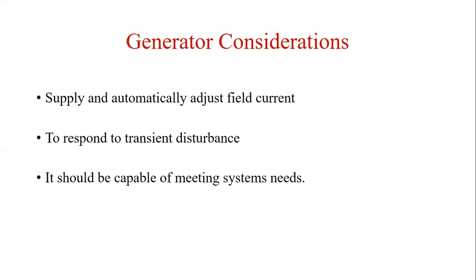In addition, the excitation system must respond to transient disturbances with field forcing consistent with the generator's instantaneous and short-term capabilities. The generator capabilities in this regard are limited by several factors: rotor insulation failure due to high field voltage, rotor heating due to high field current, stator heating due to high armature current loading, core heating during unexcited operation, and heating due to excess flux. The thermal limits have time-dependent characteristics and the short-term overload capability of the generators may extend from 15 to 60 seconds.